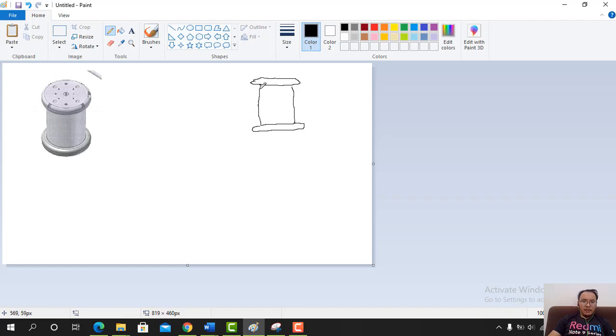The connection of the test transformer will be directly to the supply. We have 3 lines: 2 lines for the supply and the last line for the grounding purpose. All of these lines will be connected to the box of the frequency converter. This is the schematic diagram for the test transformer, where all the cable lines will use about 2.5 mm square sizing.